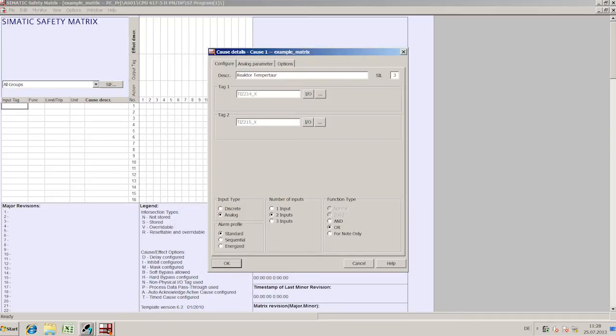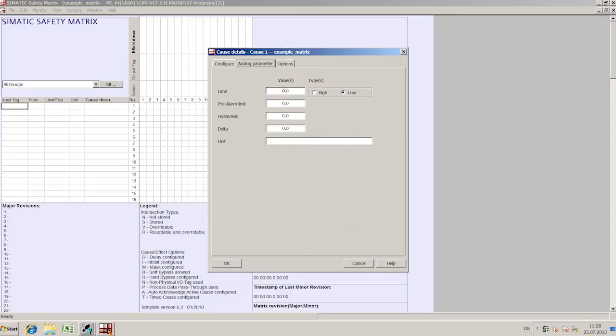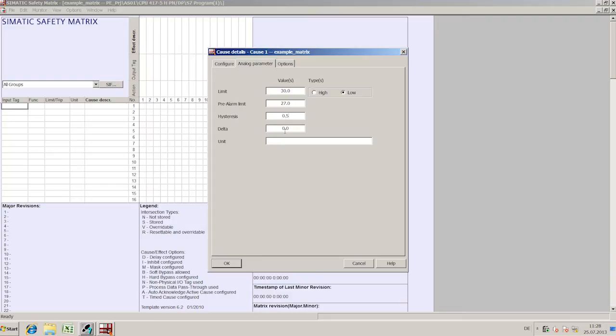A cause can have an effect on up to four different actuators. Causes can also be combined together in selection groups. In this way, a two-from-three selection is possible, for example.